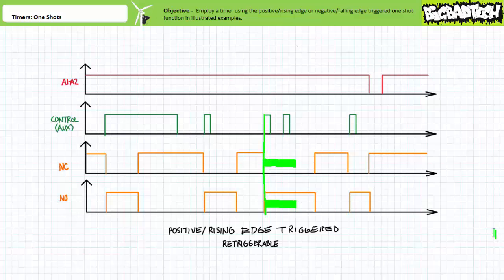Ordinarily, the one-shot would execute a 5-second one-shot after the receipt of the first positive edge. The retriggerable one-shot, however, instead of ignoring the additional input during the ongoing one-shot, basically dishes out 5 more seconds of one-shot as we'd expect. As previously, if the timer ever lost power during an ongoing one-shot, the ongoing one-shot would be canceled and reset, and all associated contacts would immediately return to their deactivated state. The restoration of power would return the timer to service.